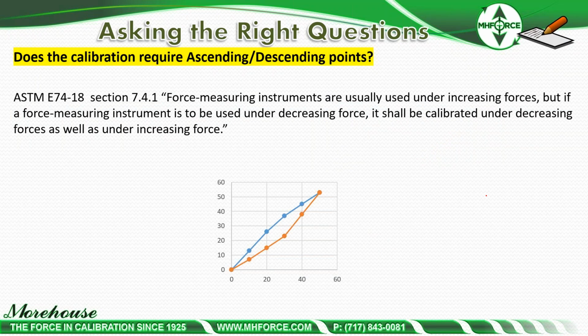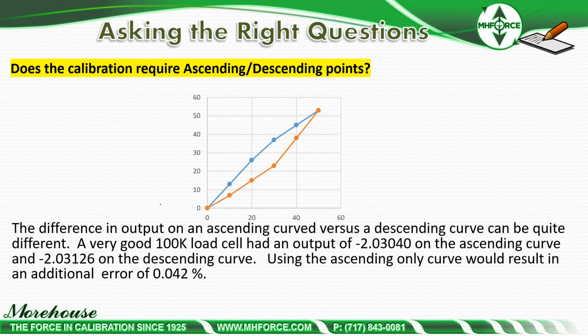So some of the things that were highlighted that are big error sources is, does the calibration require ascending and descending points? Back to E74, it is 7.4.1 and 18. This is a new change. Force measuring instruments are usually used under increasing forces, but a force measuring instrument to be used under decreasing force, it shall be calibrated. This was in the notes section as it should, and it became a shall. So no longer are weasel words in the standard as far as descending. If you're using it for descending, you must have it calibrated in descending.